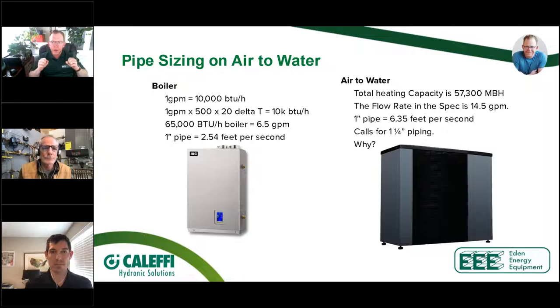T, not 14. Where people go wrong is they assume at 57,000, they've been taught with boilers that 3/4 inch PEX, 65,000 BTUs. So they throw a piece of 3/4 inch piping on this, and then you immediately kill that air to water or water to water unit. You can't even put 1 inch on a 6-ton air to water unit, but if you put 1 inch on the equivalent boiler, I mean, that's plenty. You don't even need piping that big for it. So understand that the reason these two things are not the same is because a heat pump doesn't lift the water 20 degrees. When your appliance can't lift the water 20 degrees, it's all math. The math changes. And again, we can spend more time on that in a different training module.